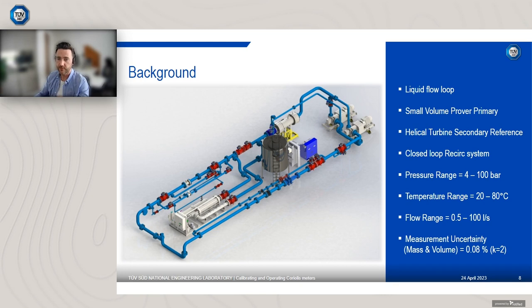So it can be changed very quickly, and the pressure can also be maintained throughout a whole calibration to plus or minus 0.25 bar. So very stable pressure. In terms of temperature, we operate between 20 to 80 degrees Celsius, and again we have inline heat exchangers. Because it's a closed loop system, it's a relatively small volume of fluid flowing around through the pumps and the heat exchangers, we can quickly change temperature. So we can go from 20 to 80 degrees Celsius in about 2 hours and achieve stability.